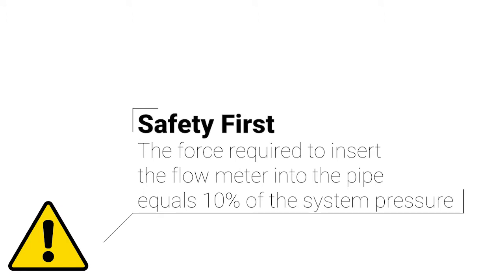Before beginning, be sure you have secure footing and are in a comfortable position to work with the flow meter. When working on an active line, you can expect one-tenth the system pressure to push up when installing or removing an insertion flow meter. Always keep your hand on top of the electronics enclosure when the clamping nut is loose.